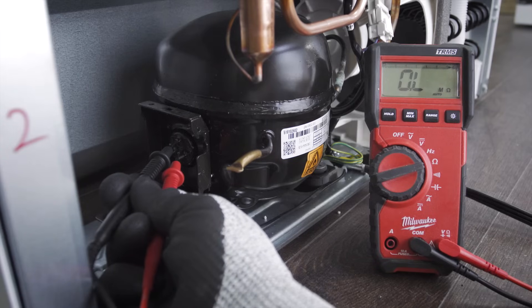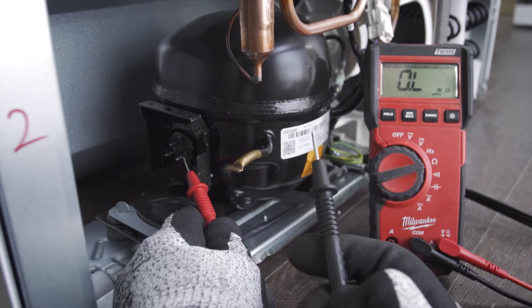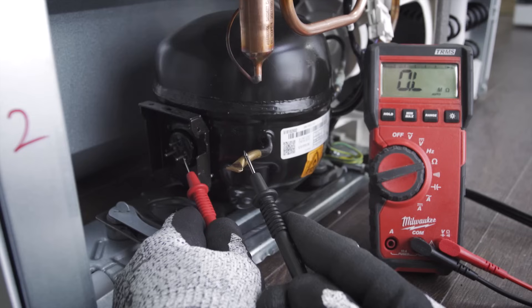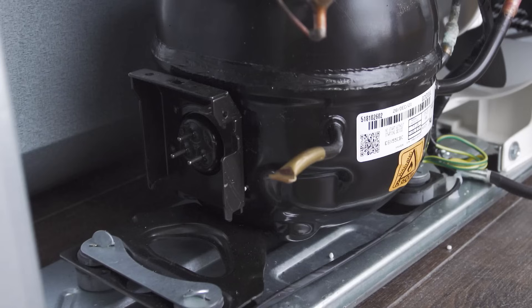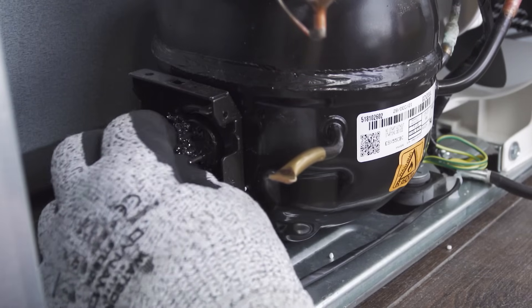If there is no continuity in any of the tests, then the compressor has failed and will need to be replaced. You can also test the compressor for a short by testing between each terminal and any bare metal on the compressor. Keep in mind this won't work on a painted surface, so you'll likely need to find the ground wire or one of the copper pipes. If there is resistance, then the windings are shorted to ground. Also check if the terminals are blackened with carbon, as this may prevent a good connection with the starter. You can use steel wool, an emery cloth, or sandpaper to clean the terminals.